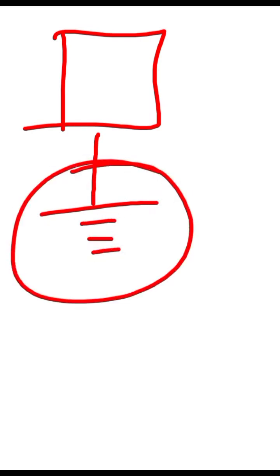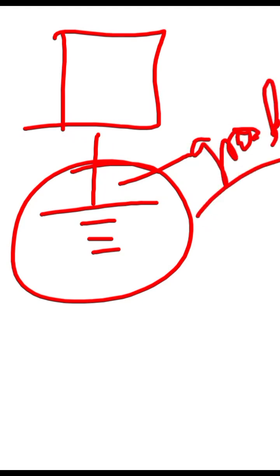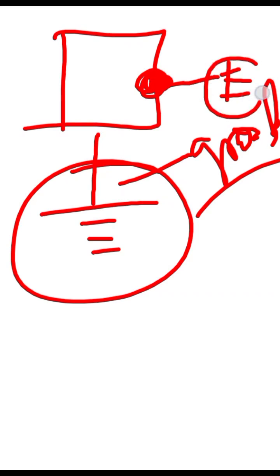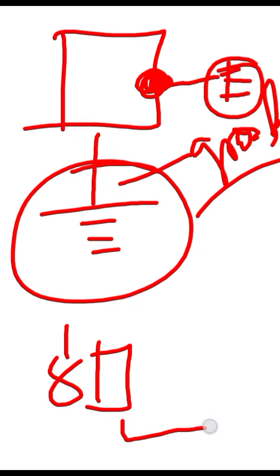So you realize that in many cases, the appliances are not independently grounded, as we're going to see in different types of system. So the grounding is done at the intake point. So you realize that the casing, the enclosure of your appliances, is the one connected to the earth wire. Near the cutout here, where we get the neutral that is going to the house is the same place you're getting the earth wire that is going to ground.